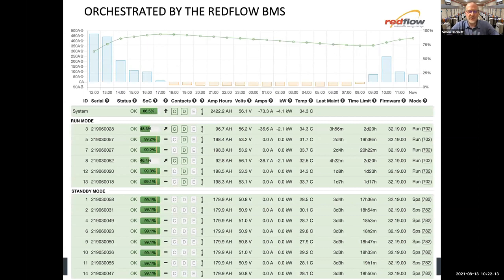One aspect of the standby power system mode, as you saw with that telco site, is that a single battery or many batteries can just be a standby power system and nothing else. Alternatively, if you have a lot of our batteries - and this is actually a picture from our battery management system showing 14 batteries running on a site that I manage - you can see the bottom 8 of them are in standby mode, listed as such, while the top 6 are running normally as batteries, what we call run mode.